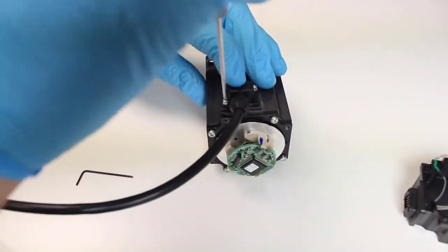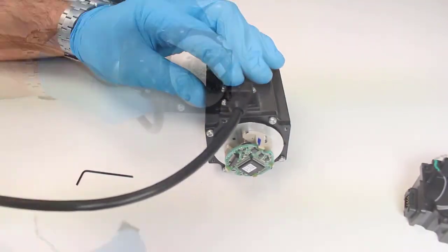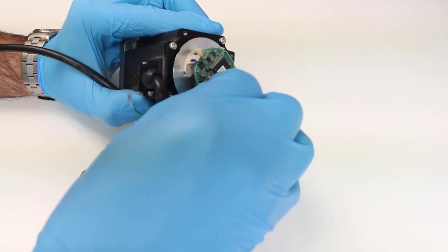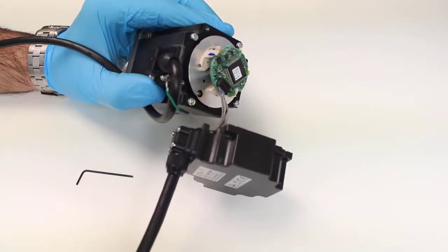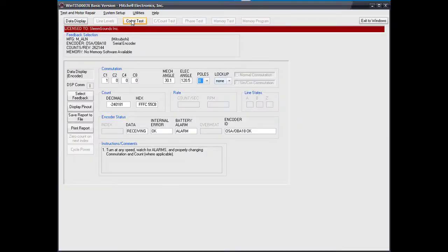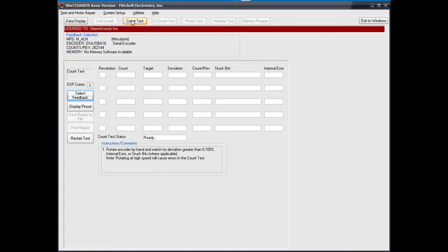Now connect the motor's power and feedback cables to our test equipment. Perform a count test in the WinTI5000JX software by rotating the motor four times. This will confirm the encoder is testing well.